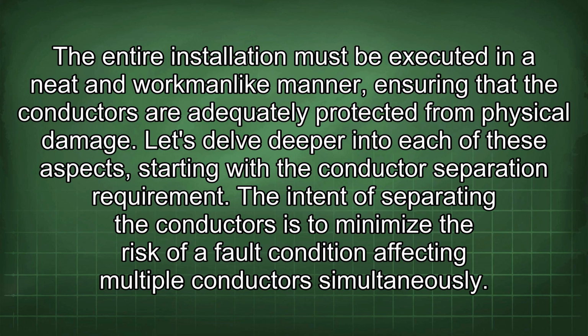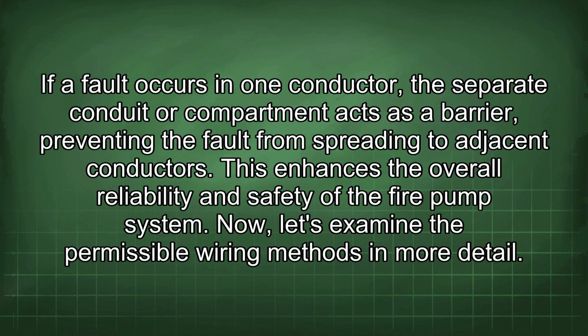The intent of separating the conductors is to minimize the risk of a fault condition affecting multiple conductors simultaneously. If a fault occurs in one conductor, the separate conduit or compartment acts as a barrier, preventing the fault from spreading to adjacent conductors. This enhances the overall reliability and safety of the fire pump system. Now, let's examine the permissible wiring methods in more detail.